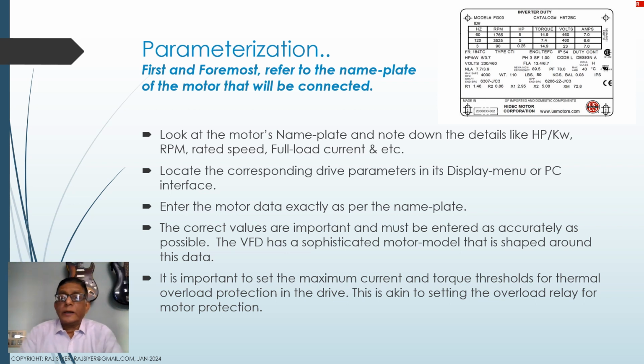Now we come to parameterization. Many of these days drives have fairly user-friendly LCD interfaces, which will group the parameters in a very logical manner. The main things to set up, of course, are the motor nameplate details. Have the nameplate details around, take a picture of it on your mobile, and then go to the VFD's parameters for nameplate, that is motor voltage rating, current rating, RPM, and all these things are mentioned. Look up the nameplate and enter the parameters.